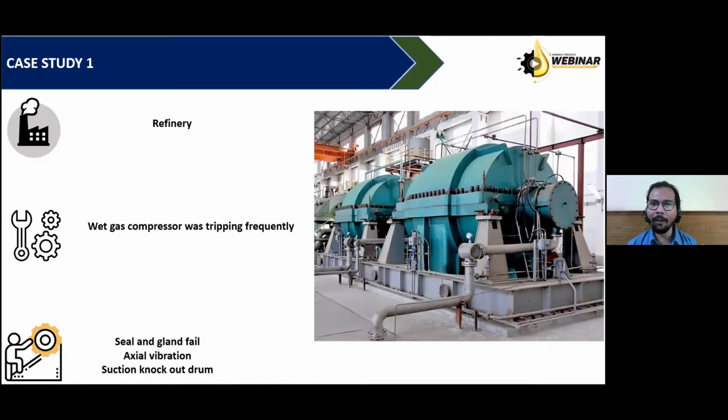When we did the in-depth analysis of the oil, we found that the viscosity of the oil was coming down even a few days after oil replacement. Then, after the elemental analysis, when we checked the oil with a gas chromatograph, we found that apart from the base oil and additives, there were n number of different hydrocarbons or chemicals present in the oil.